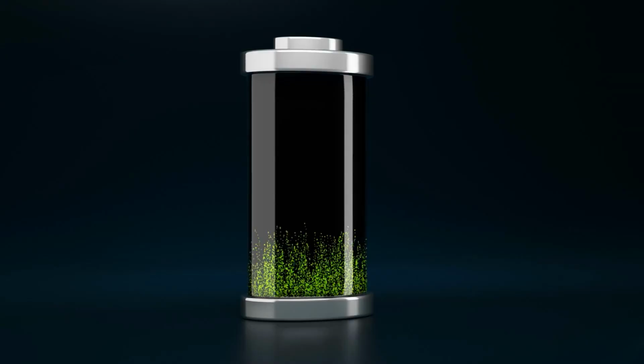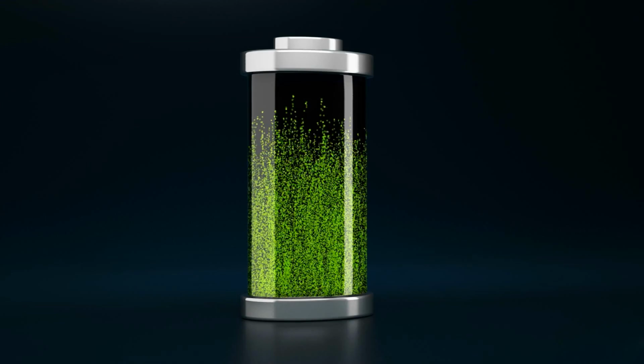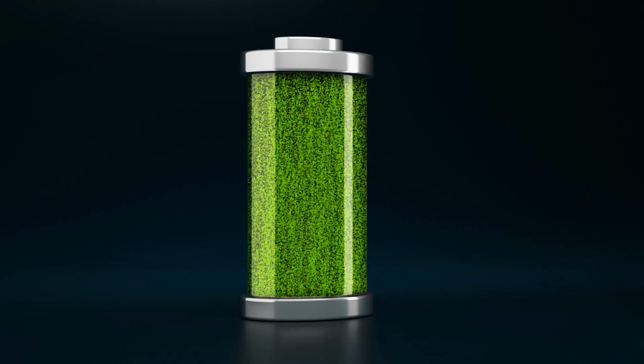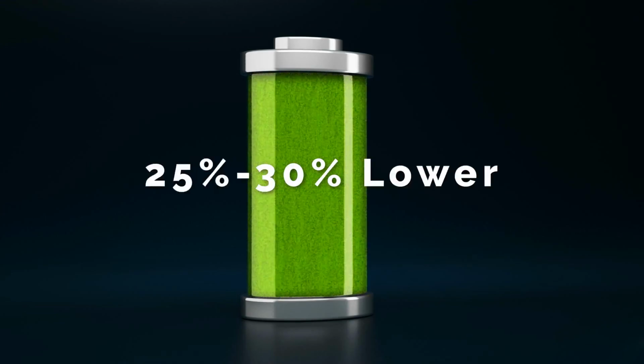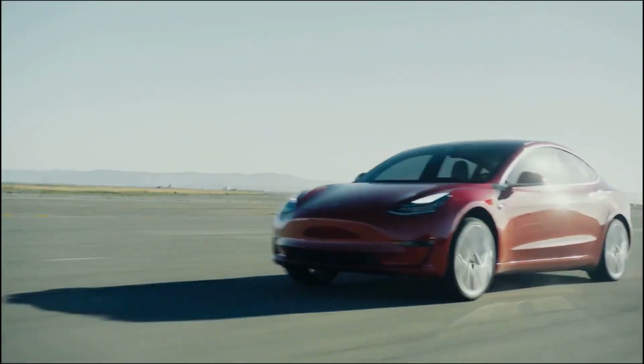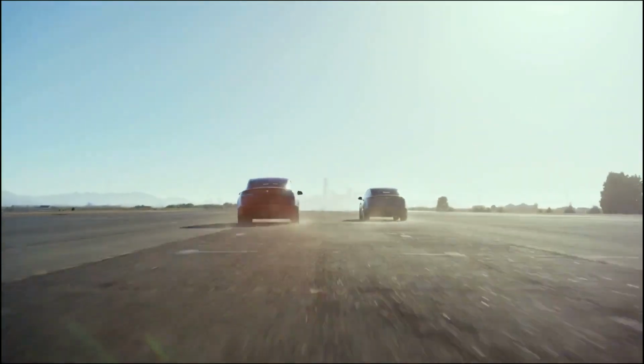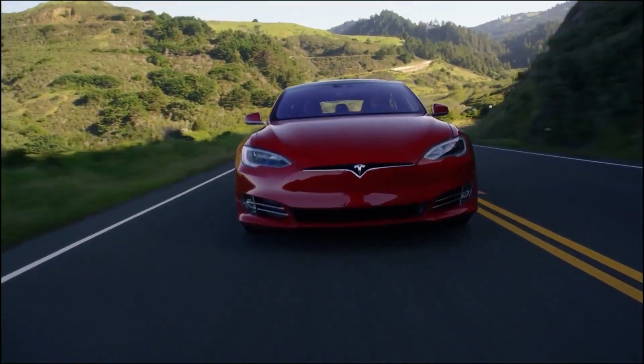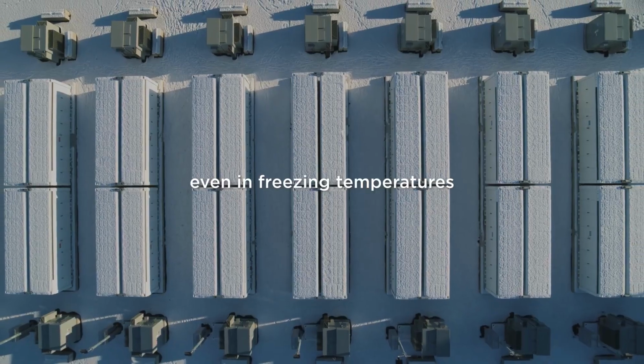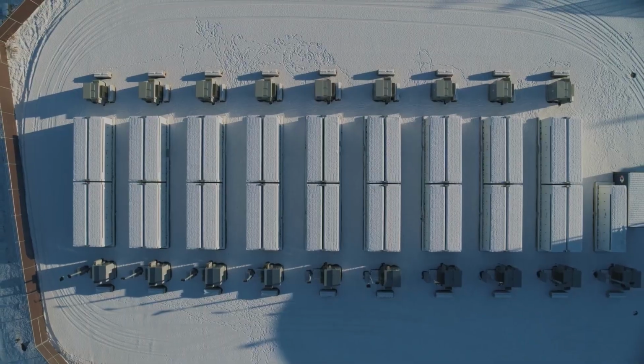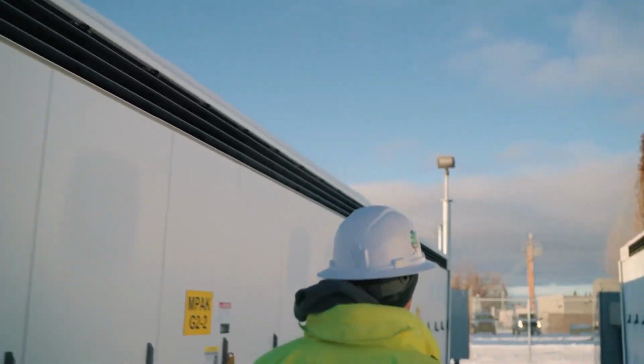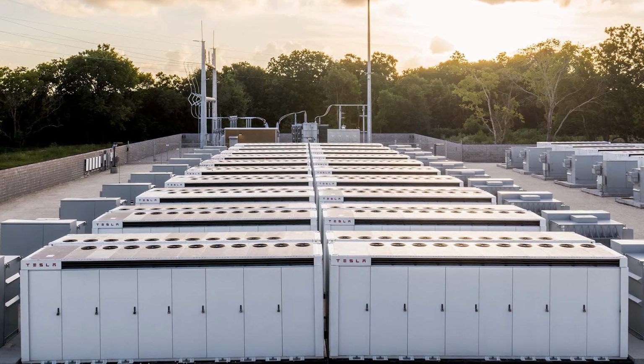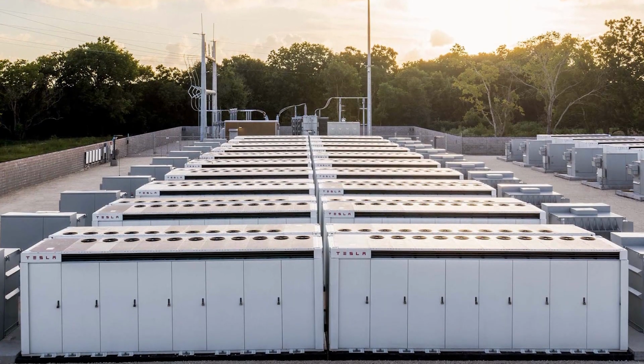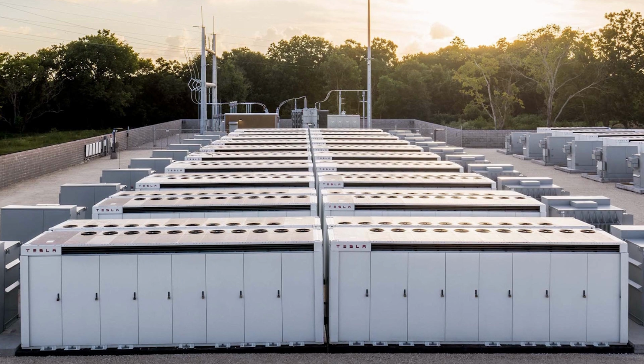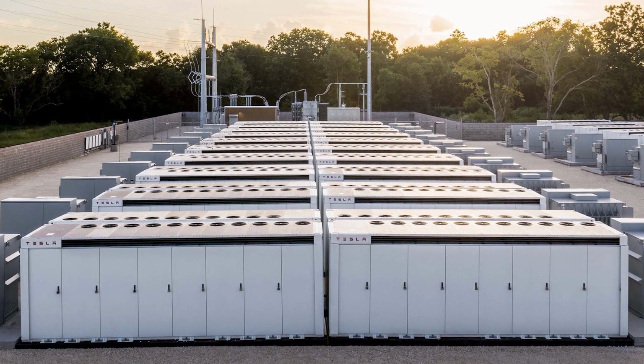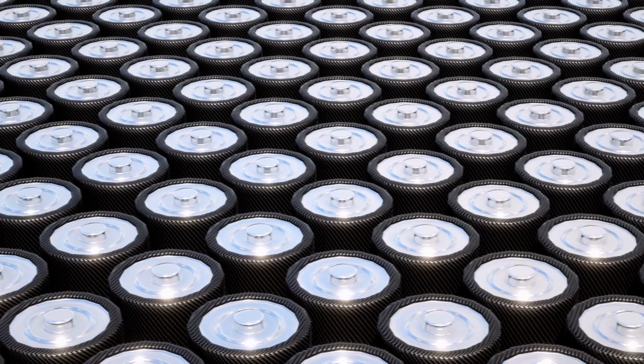The trade-off is a reduced energy density. The storage capacity per kilogram of cell material is about 25 to 30% lower. In a vehicle, that translates to lower range and slower acceleration. But a Megapack does not move, so all they need to do is build the box bigger and put more batteries in it. In this case, Tesla went so much larger with the new Megapack that it actually exceeds the capacity of the older unit, even with the lower density battery cells.